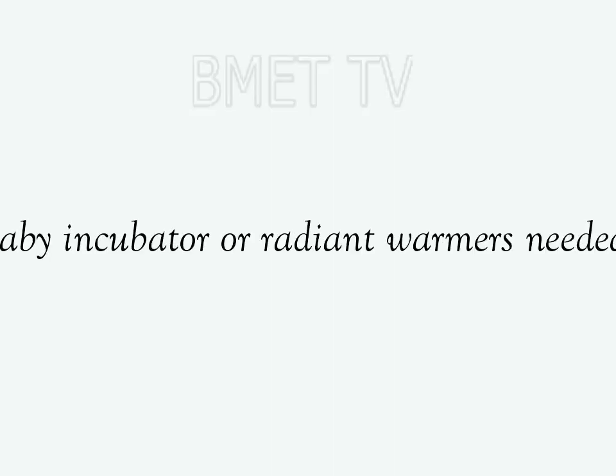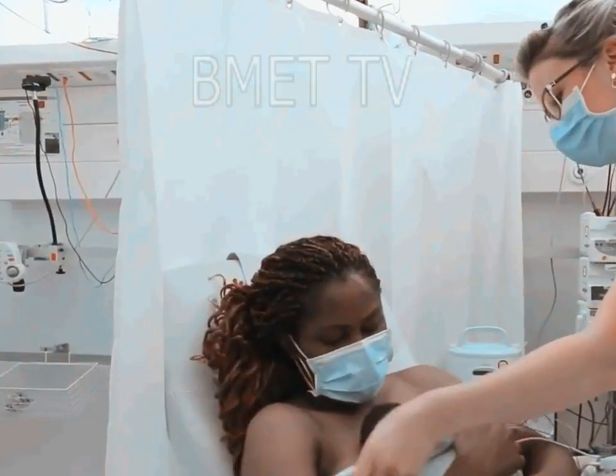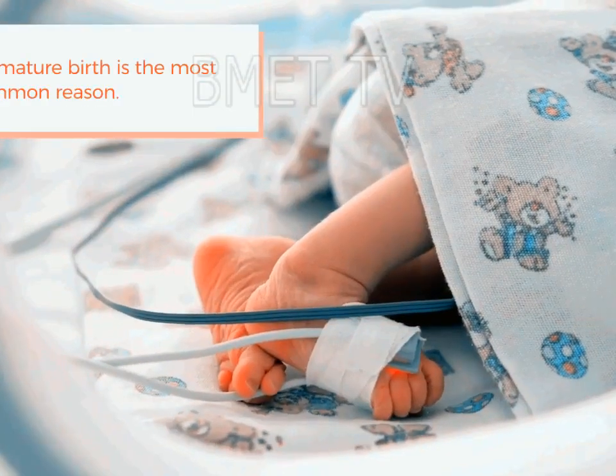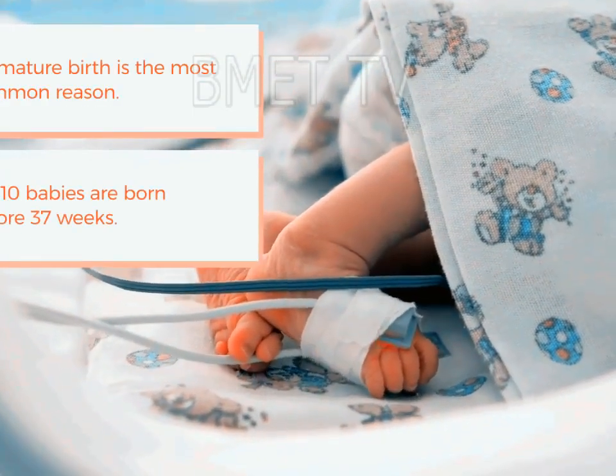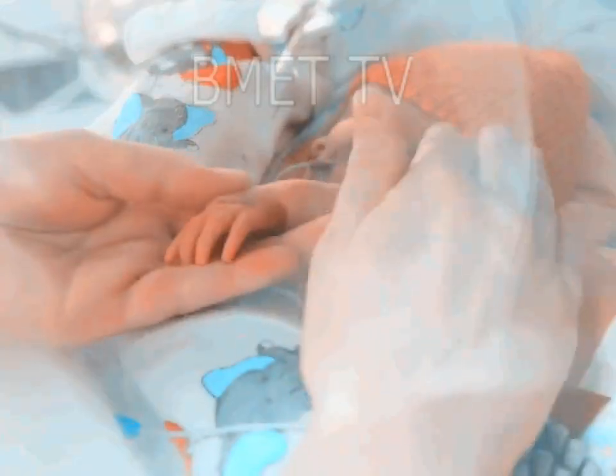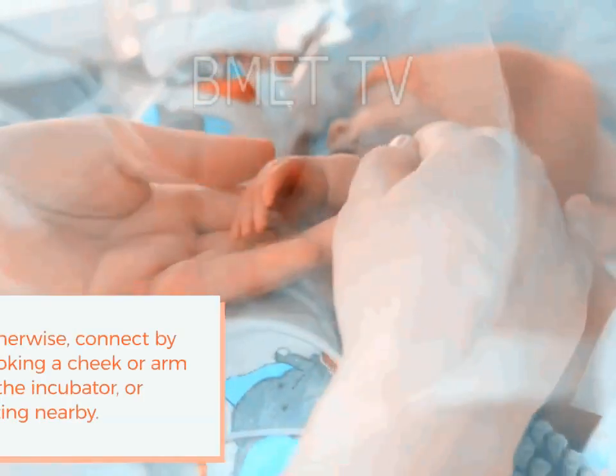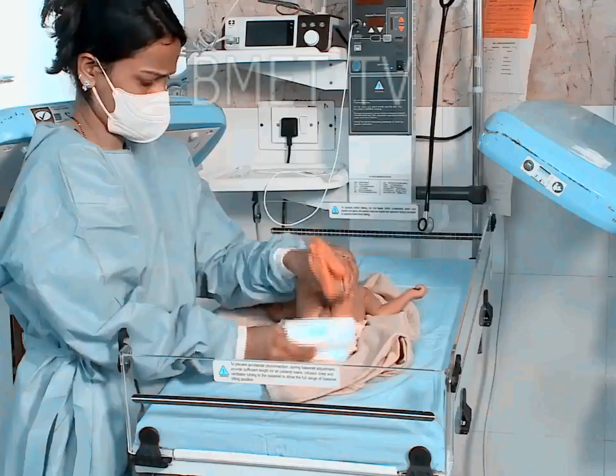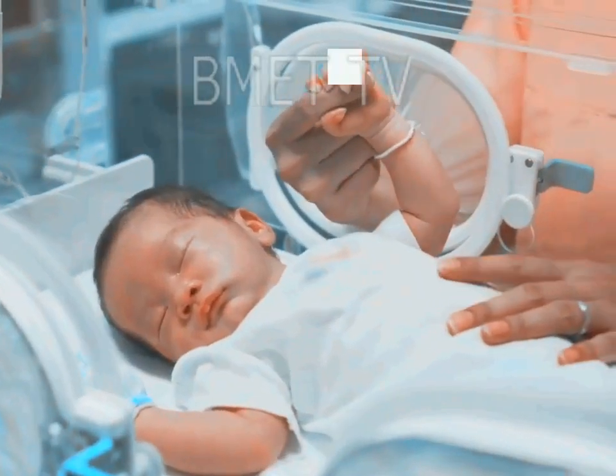So why are baby incubators or radiant warmers needed? Incubators and radiant warmers are used to maintain the body temperature of newborn infants. This is best done so that the energy expended for metabolic heat production is minimized. The heat output of these devices is usually regulated by servo control to keep the skin temperature constant at a site on the abdomen where a thermistor probe is attached. In incubators, air temperature can also be controlled as an alternative to skin temperature servo control.